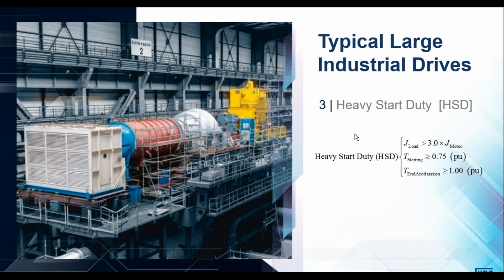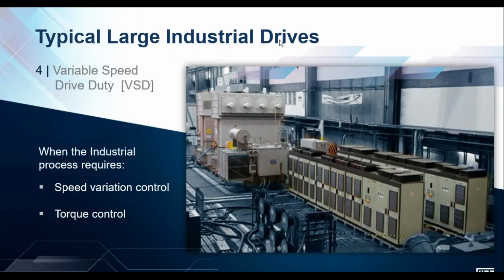Right, then we define heavy start duty as high load inertia greater than 3 times the motor's inertia, starting torques that could exceed 75% of the nominal rating, and where end of acceleration could also possibly exceed the nominal rating of the machine. A good example here would be a ball mill or a crusher, where you have a large inertia and there are short time overloads required both during starting and possibly during operation of the load. And then the final classification is applications that require speed control or torque control. In this case, the example would be needing to use a variable speed drive in continuous operation or directly connected to the motor permanently.